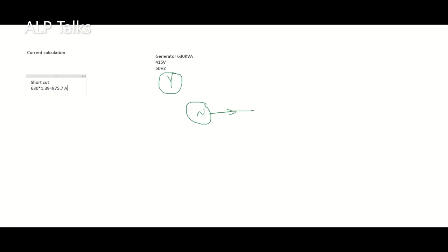So here, 875.7 amperes is the current. What is 1.39? For calculating current, we have a formula: kVA into 1000 divided by root 3 into volts.